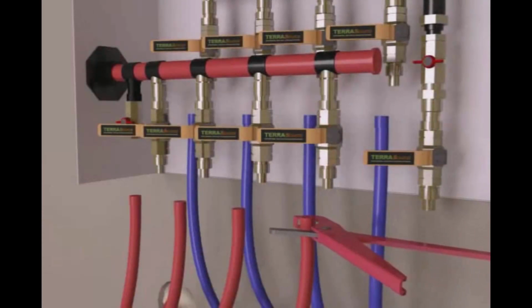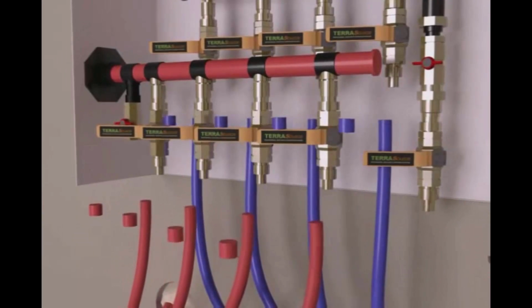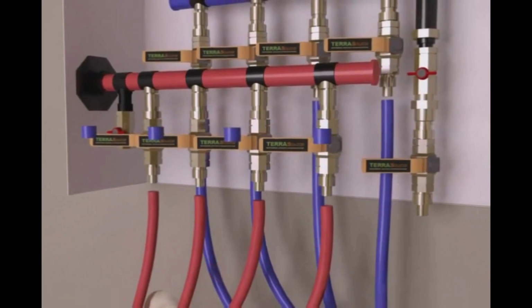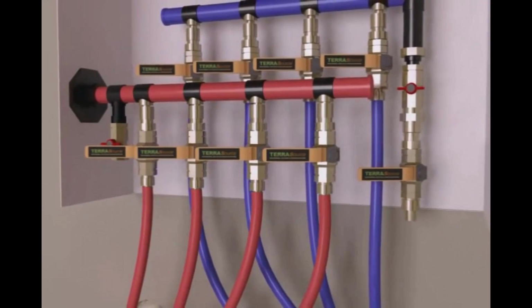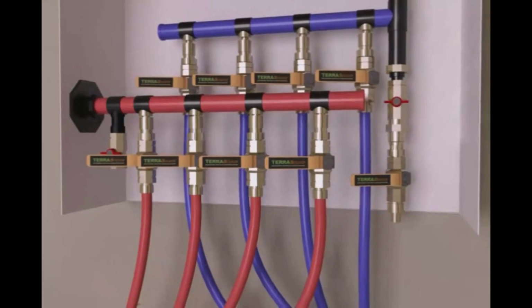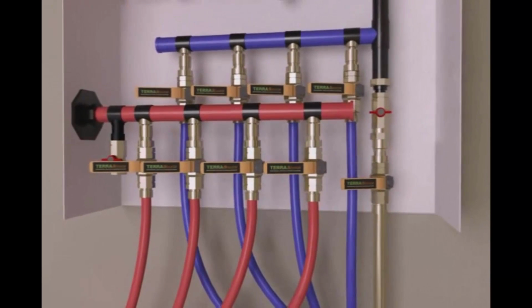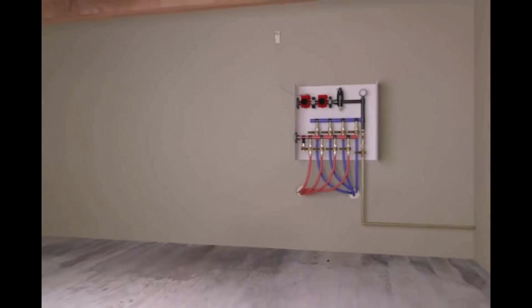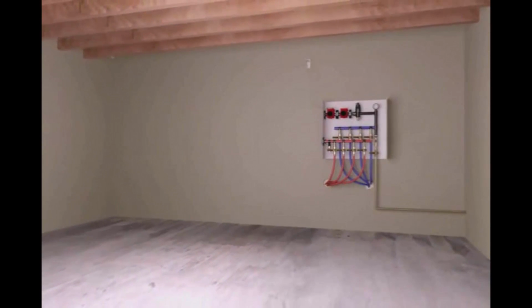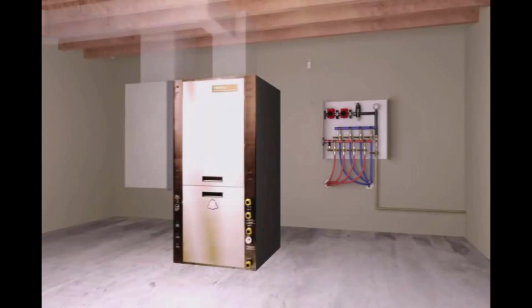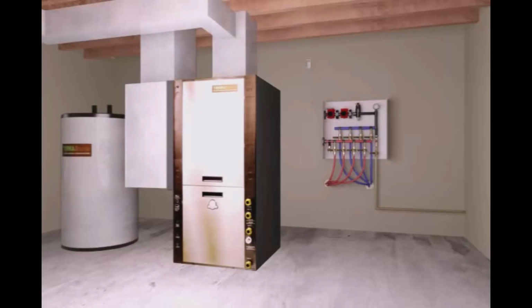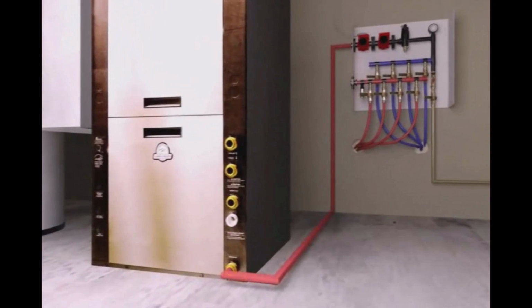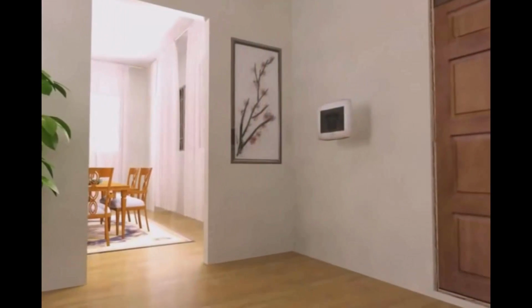Inside the house, we will connect the loops to the manifold. First, cut off any slack on each loop end. Each loop has a quick connect fitting that inserts into the manifold port. Then a fresh water source is connected to the manifold. This will be used to fill the loops later. The ductwork, manifold, and optional water heater are now connected to the heat pump through easily identified connections. Next, connect the thermostat to the color-coded thermostat wire provided. Both the color-coded thermostat wire and control wire from the manifold are plugged into the heat pump.